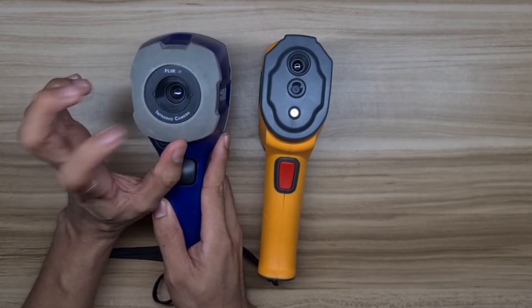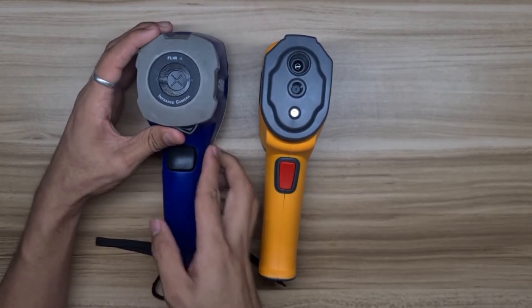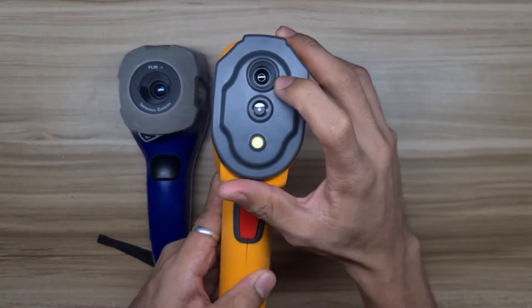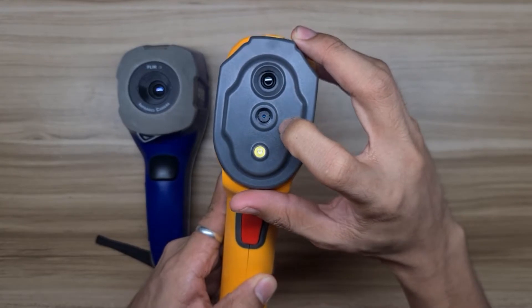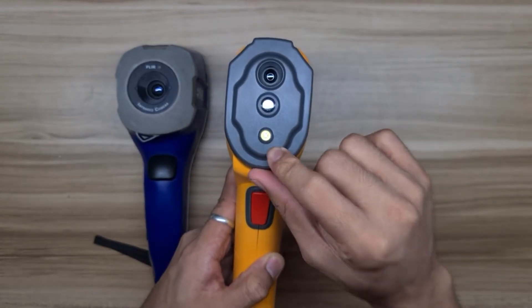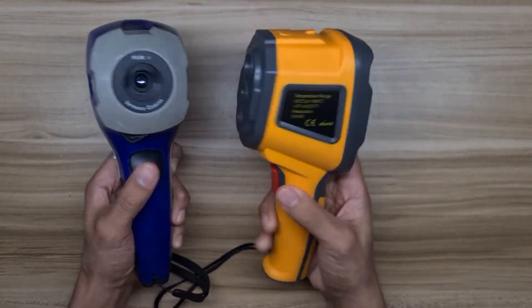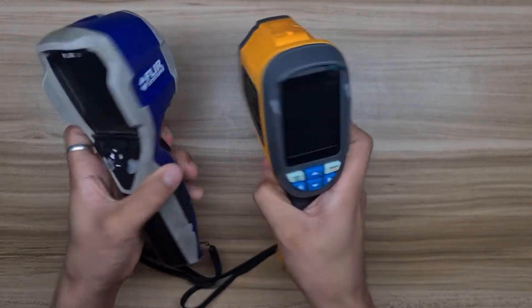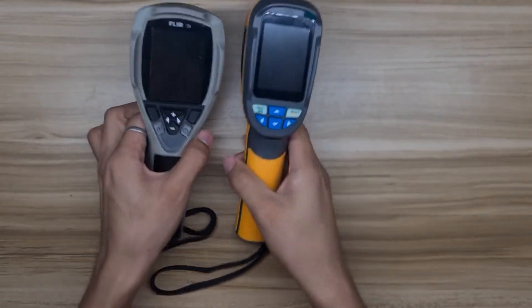This cover is good since it is an expensive device and costly to repair once damaged. The FLIR i3 only has a thermal camera, while the HT-02 has a thermal camera, a visual light camera, and an LED light which can be used while doing inspection and testing. Both have a button in front for capturing, which makes the device ergonomic to handle. Both also have a wrist strap, which is good when working on inspection around the plant.